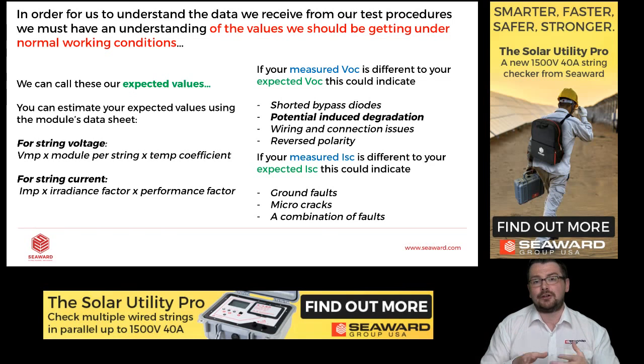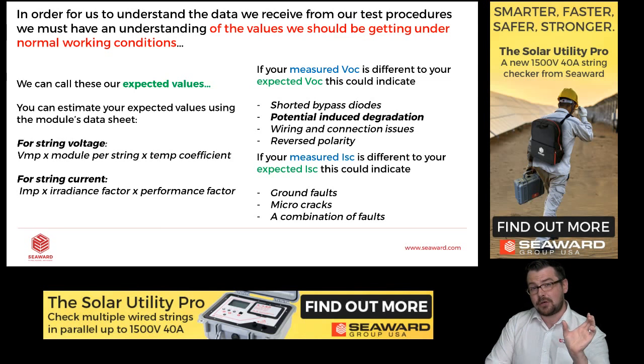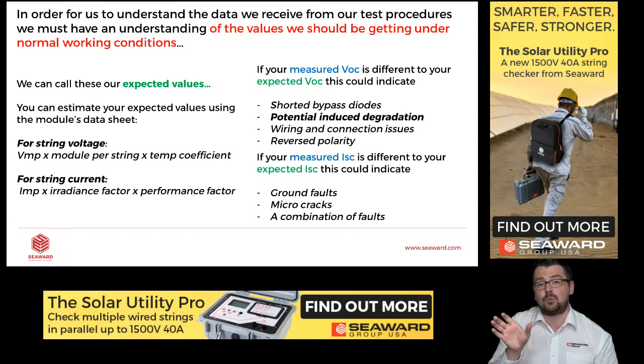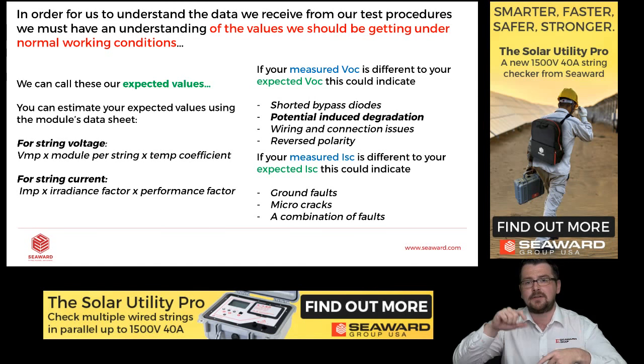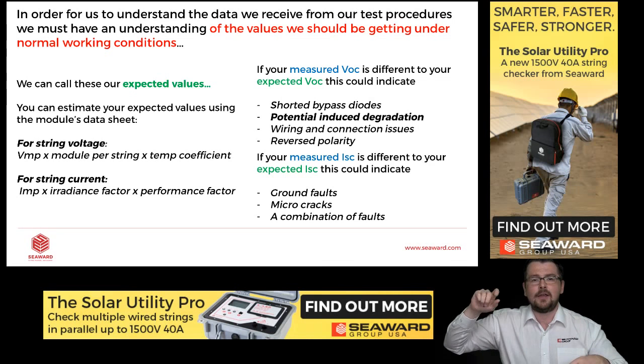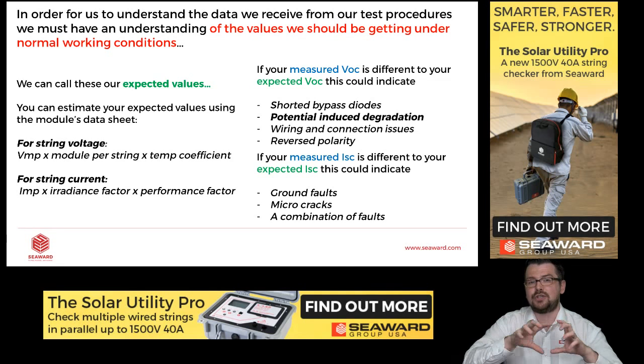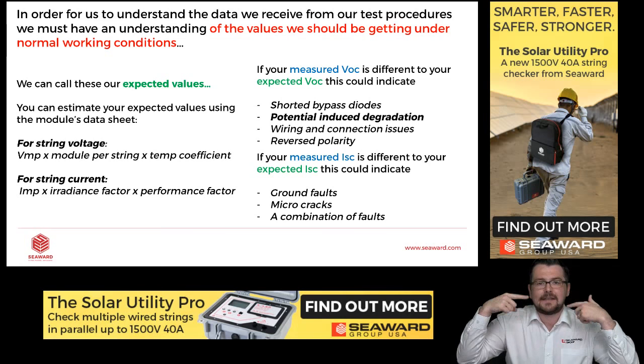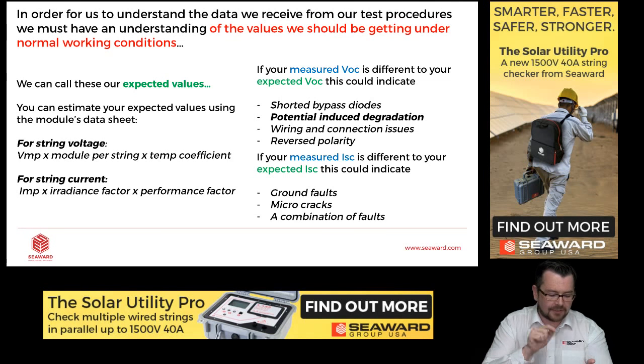For string current, we can do a very similar equation. So we take the STC short circuit current and we multiply by the irradiance factor. Now the irradiance factor is whatever irradiance you're measuring right now divided by STC, standard test condition irradiance, which is 1000 watts per meter squared. So if you're testing at 500 watts per meter squared, divided by 1000, times the STC ISC, which in this instance, let's say is 8, that would be 4 amps. So when we do our test, we should see 4 amps. So with these figures in mind, before we've even begun testing, when we run the test, we can know if we're in line with what we expect.